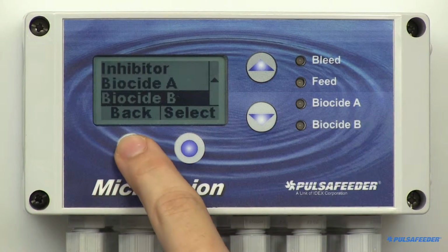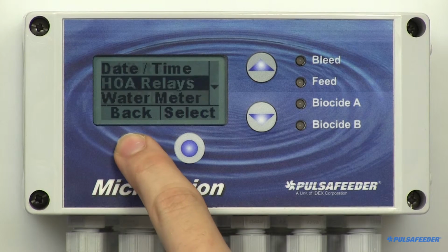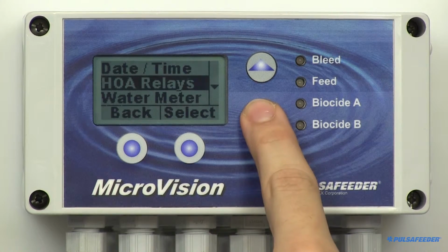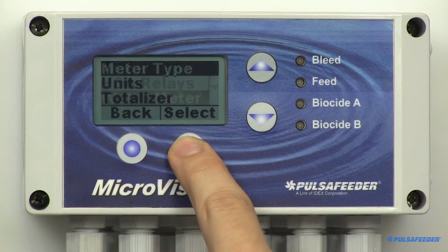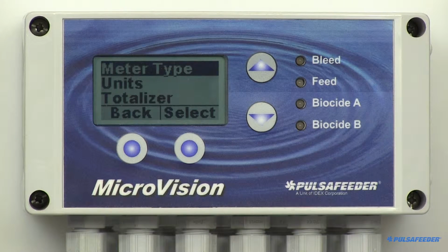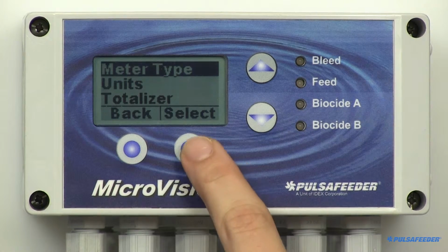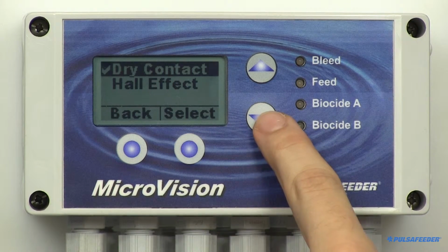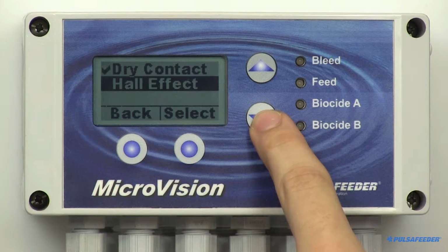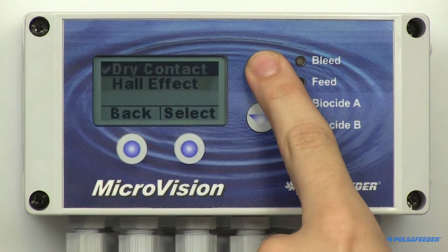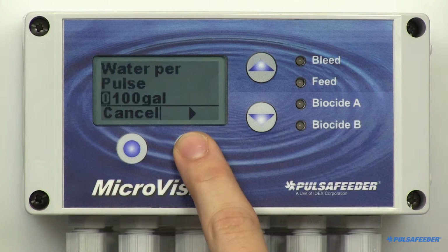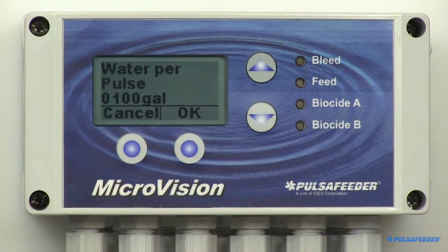Now we will cover the water meter settings. Press the back button and arrow down and select water meter. The first menu selection is meter type. Press Select, and you'll see both dry contact and Hall effect. If you have a dry contact style, press Select, and then enter the number of gallons per contact using the arrow and soft buttons, and press Enter.